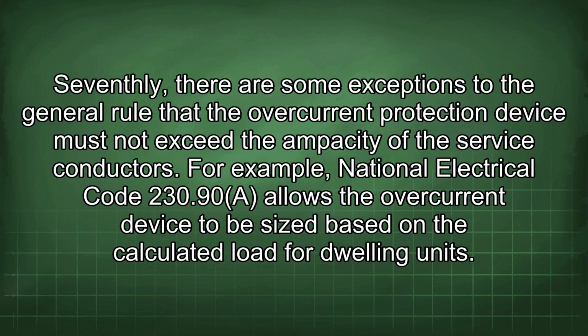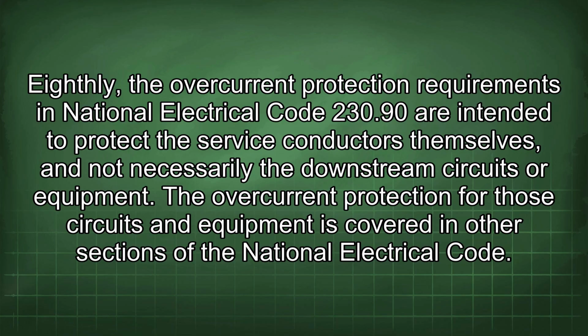Seventhly, there are some exceptions to the general rule that the overcurrent protection device must not exceed the ampacity of the service conductors. For example, National Electrical Code 230.90 allows the overcurrent device to be sized based on the calculated load for dwelling units. Eighthly, the overcurrent protection requirements in National Electrical Code 230.90 are intended to protect the service conductors themselves, and not necessarily the downstream circuits or equipment. The overcurrent protection for those circuits and equipment is covered in other sections of the National Electrical Code.